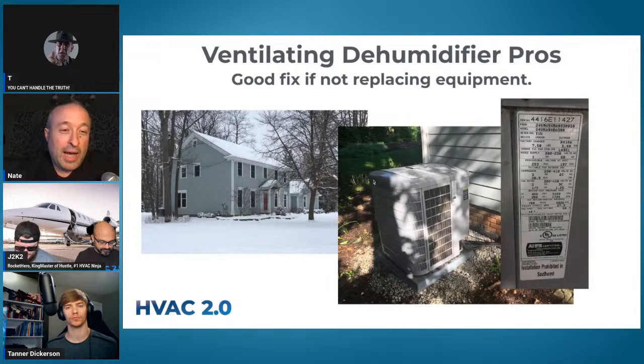The humidity was just out of control in this house. It's so frustrating—it's oversized even though it's variable speed, so variable speed will not save your butt. It's important to note this is a 4-ton unit on a 3,000 square foot house, and it's way too big. It was a real problem.